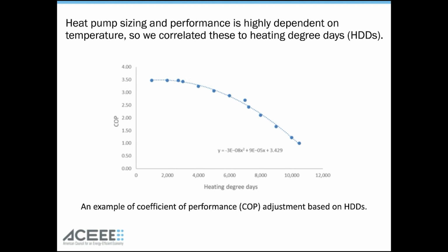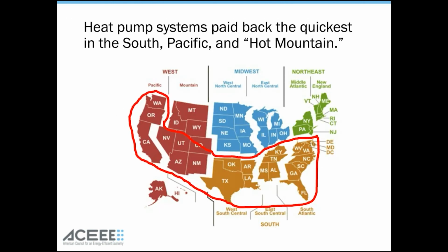CBECS doesn't have data like average winter temperature, but they do have something called heating degree days. Essentially, the higher the number of heating degree days, the colder the area you're in. So we correlated performance, as you see in this chart, with COP, and sizing with capacity, using the heating degree days.